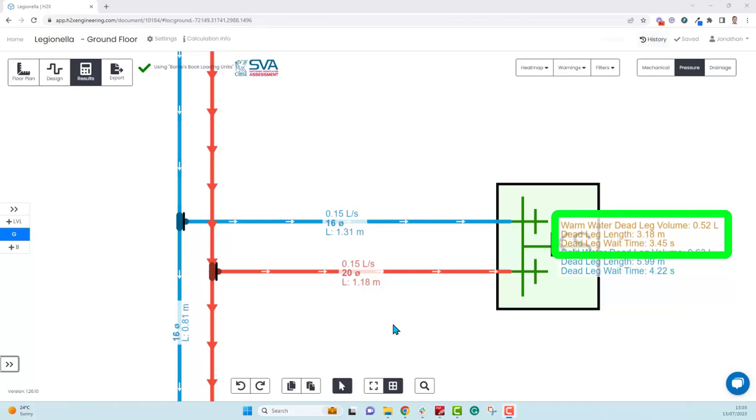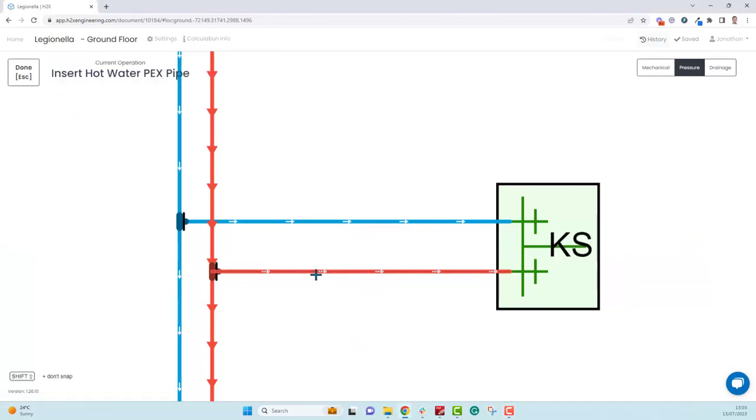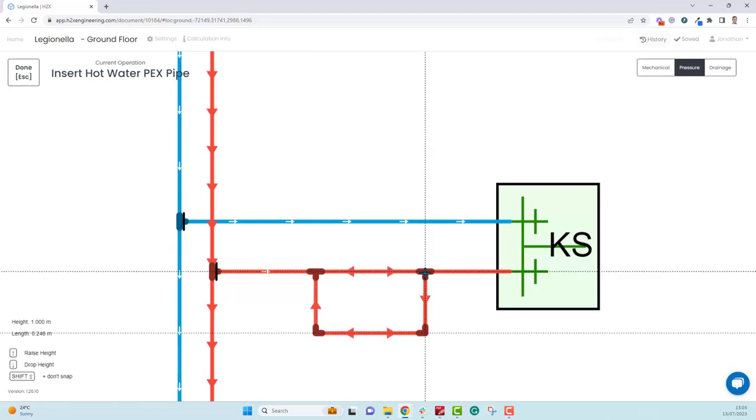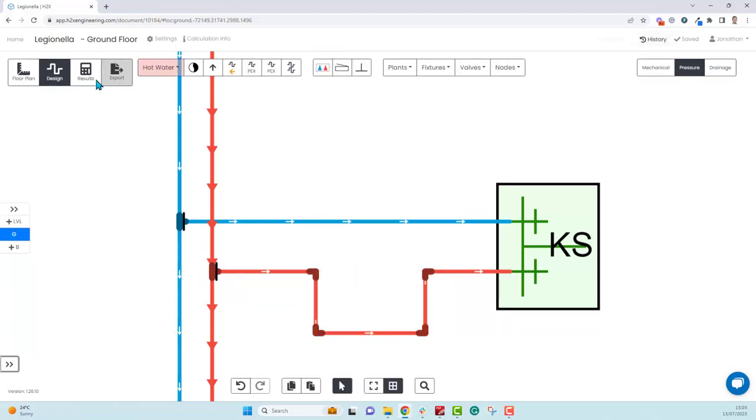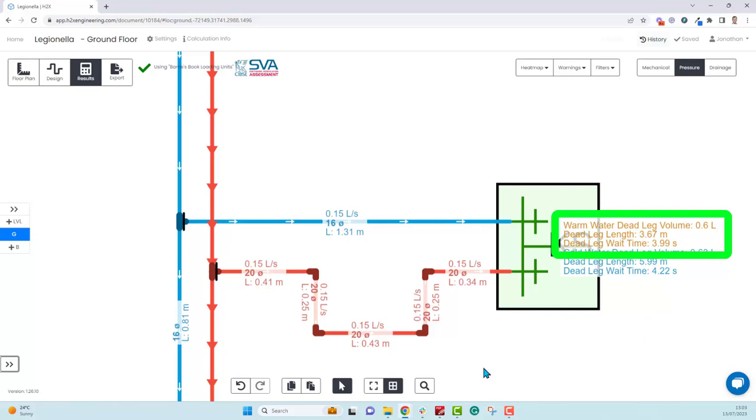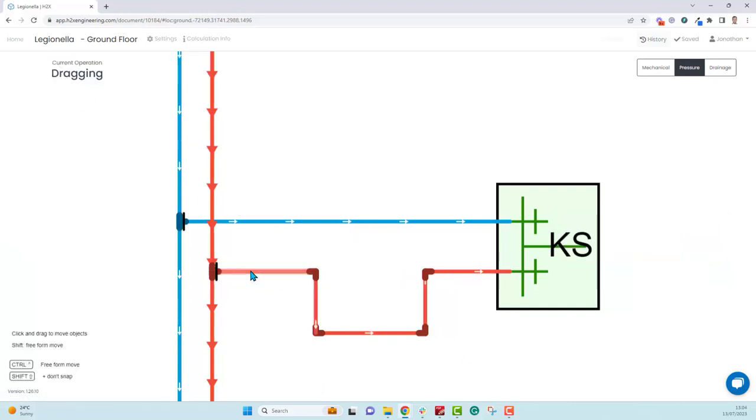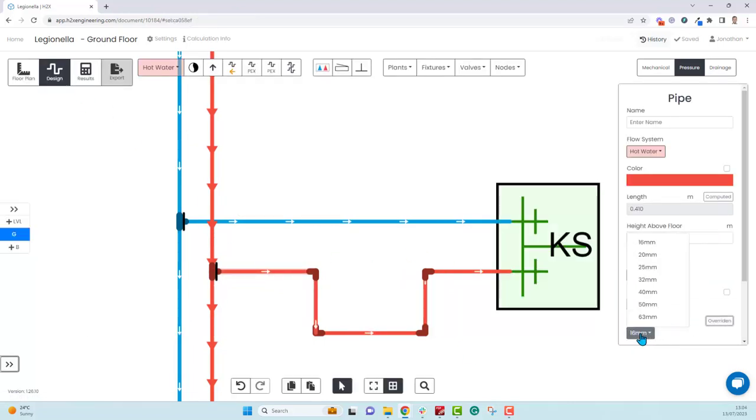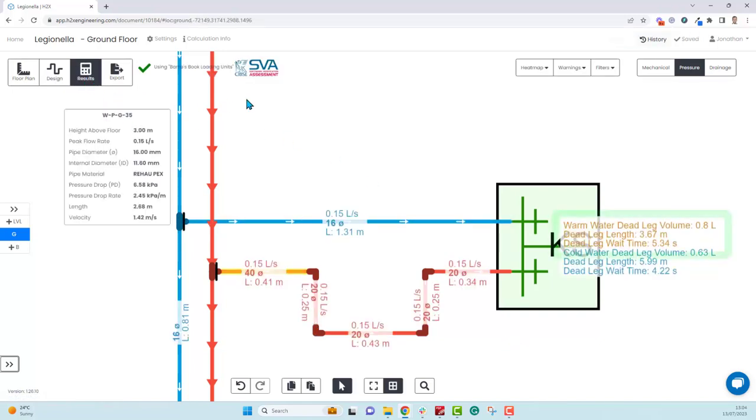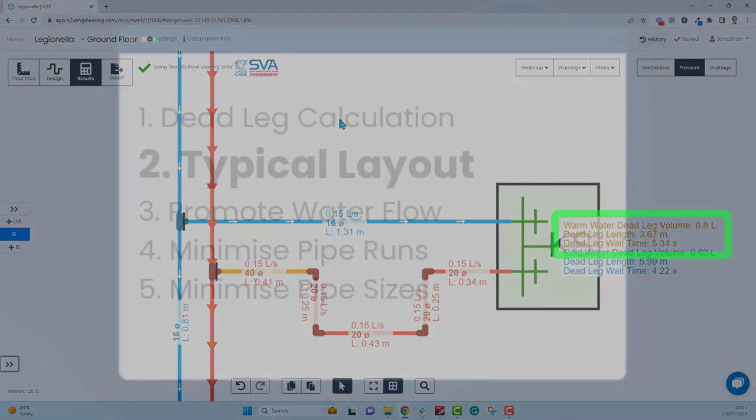Let me show a couple of examples. If we come back to the design and add some extra length onto the dead leg, we can see straight away that the dead leg volume has increased and the wait time has increased too, highlighting that you want the pipe layout to be as direct as possible. As another example, let's say we increase this pipe size to 40 millimeters. Once again, you can see the volume has increased significantly just from that small pipe being upsized.